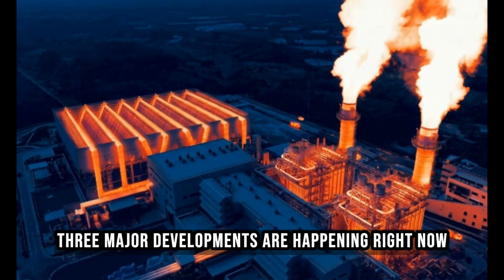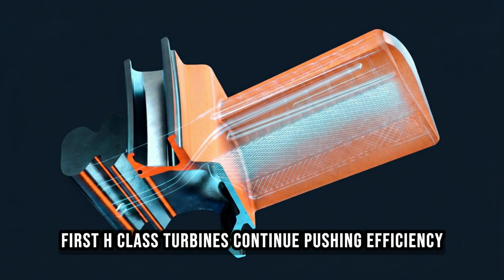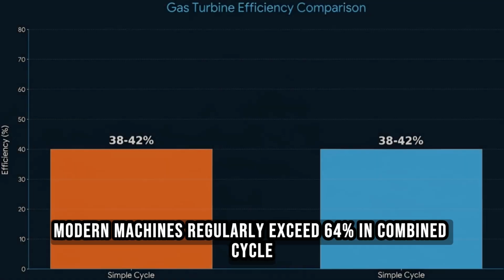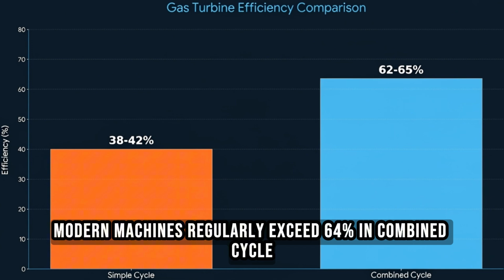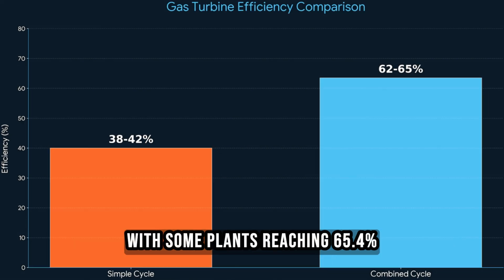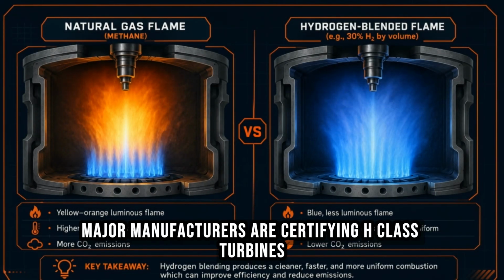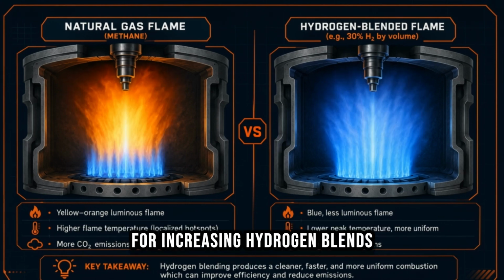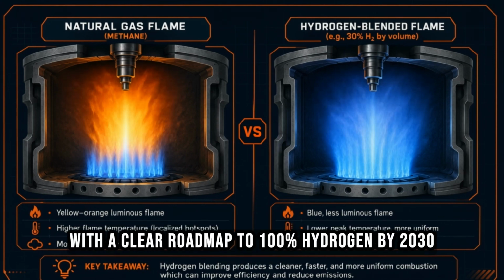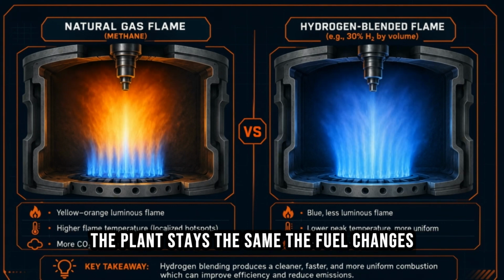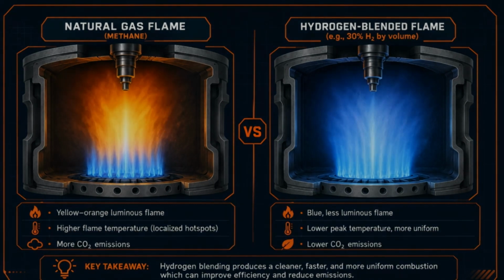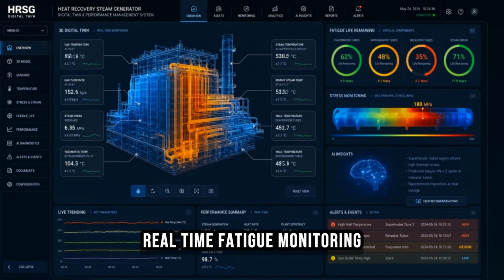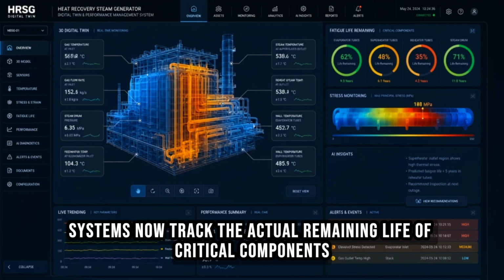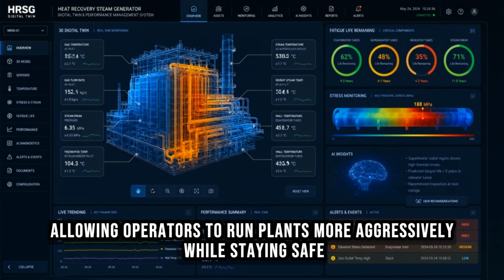3 major developments are happening right now. First, H-class turbines continue pushing efficiency. Modern machines regularly exceed 64% in combined cycle, with some plants reaching 65.4%. Second, hydrogen readiness. Major manufacturers are certifying H-class turbines for increasing hydrogen blends with a clear roadmap to 100% hydrogen by 2030. The plant stays the same, the fuel changes. Third, digital life management. Real-time fatigue monitoring systems now track the actual remaining life of critical components, allowing operators to run plants more aggressively while staying safe.